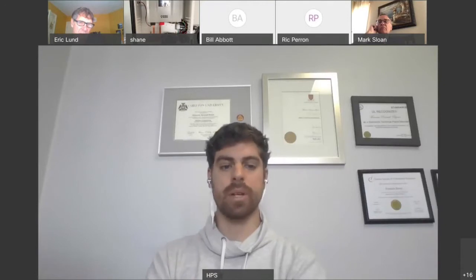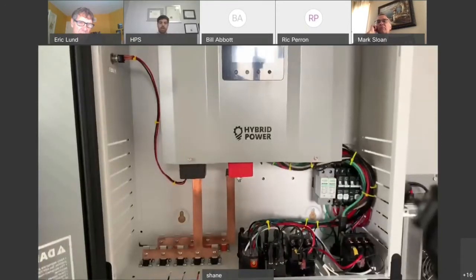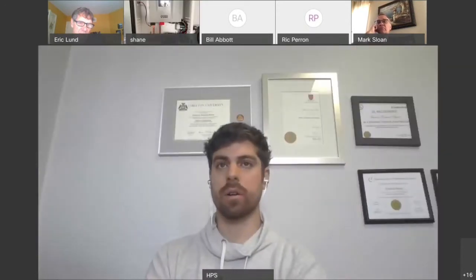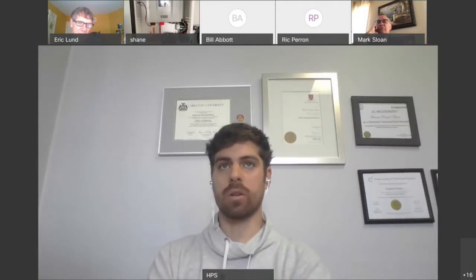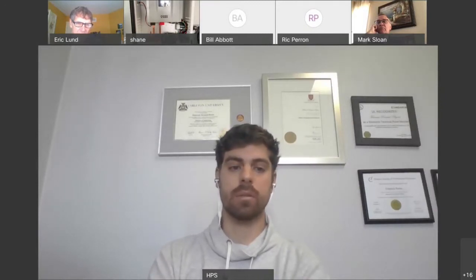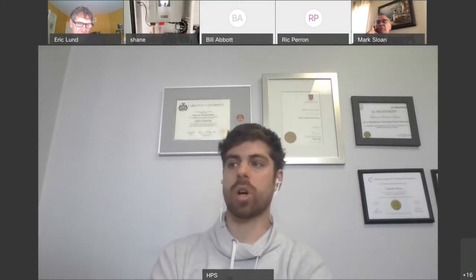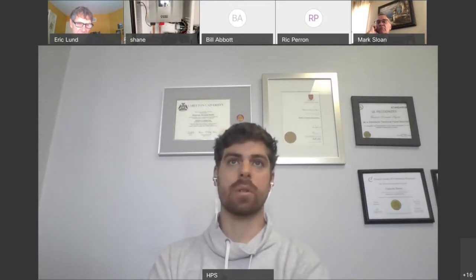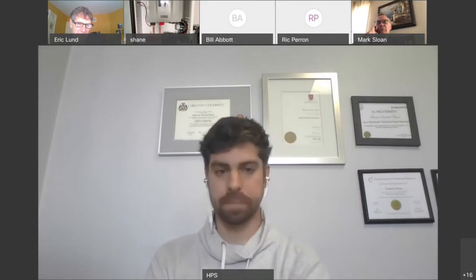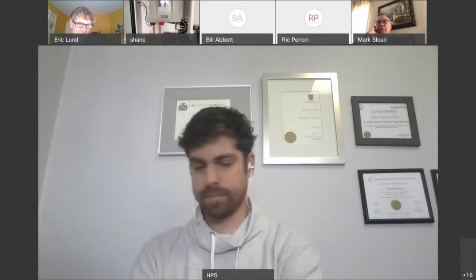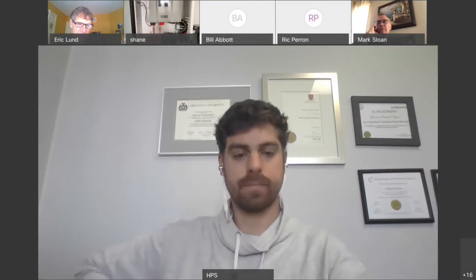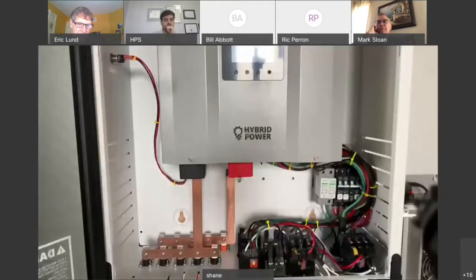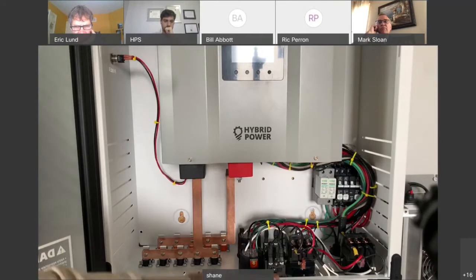So what's going to happen is when the AGS turns on and tells the generator to turn on, it'll wait until the system actually starts seeing an AC input. It'll actually wait 60 seconds before the charger starts charging up those batteries, to give your generator time to warm up. That's right. So that's pretty much everything that's underneath. There's also some relays and some thermal protection right here, the 30 amp thermal relay.